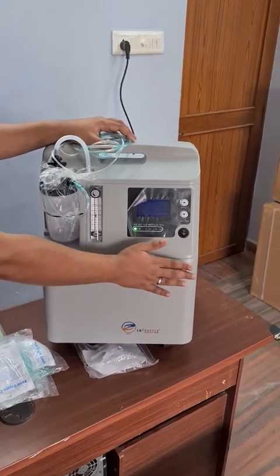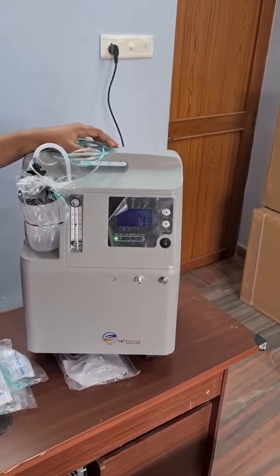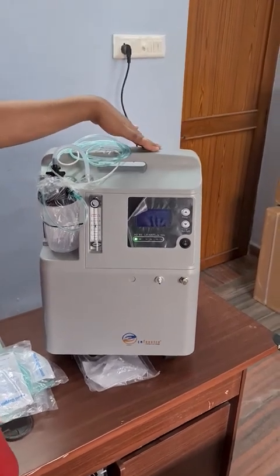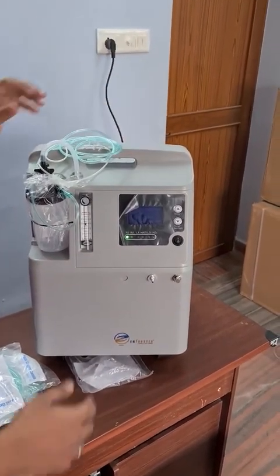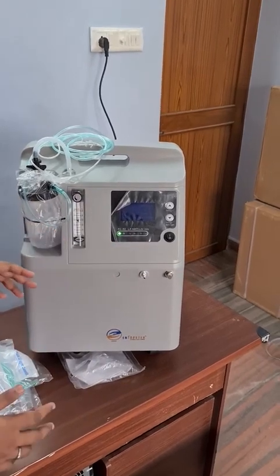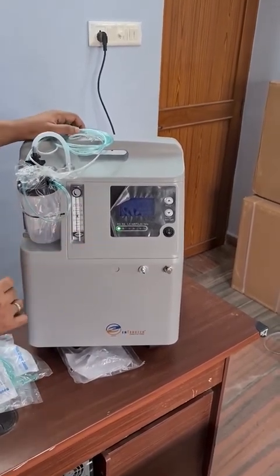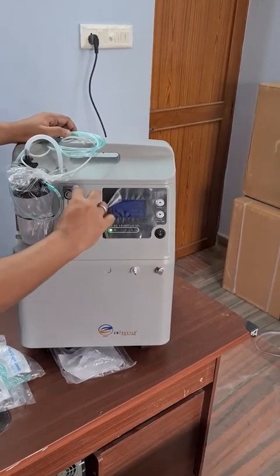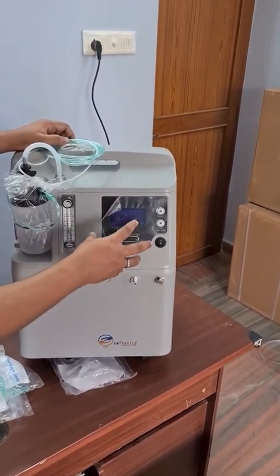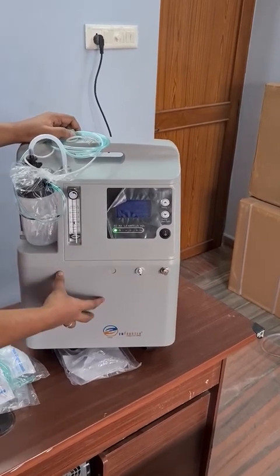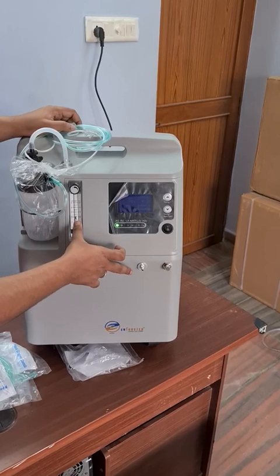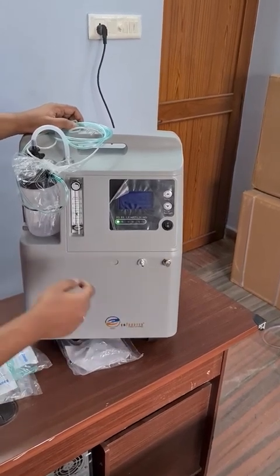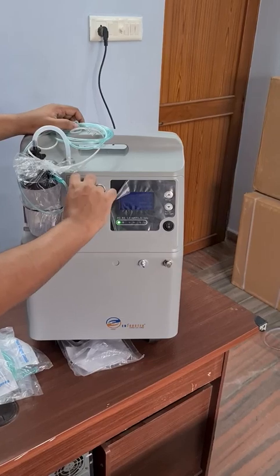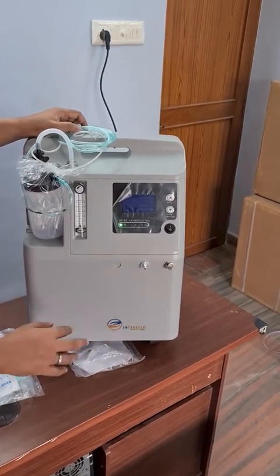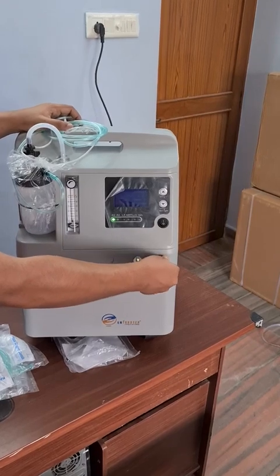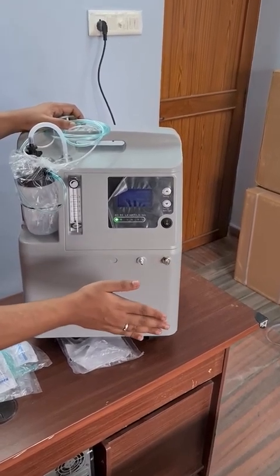Now let us see about the nebulization port also. As I told you in the beginning of the video, the main advantage of our brand of concentrator is that you can use it as a concentrator, and whenever you want you can also use it as a nebulizer. So how are we going to use the nebulizer? Before using the nebulizer, make sure to bring the oxygen flow rate to 0, because both the concentrator and the nebulizer use the same compressor. If you use both operations together, the compressor will take a heavy load. So always remember to set the concentrator to 0, and once it comes to 0, you can rotate the nebulization port anti-clockwise. And as you can see, the nebulization has started.